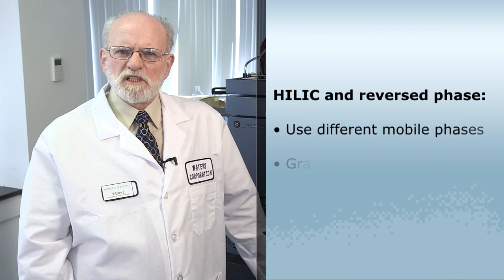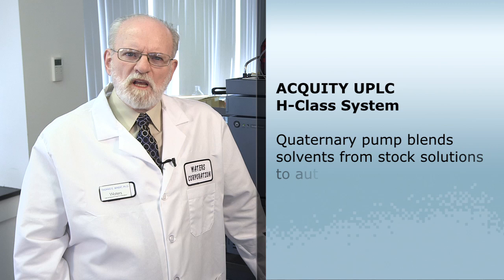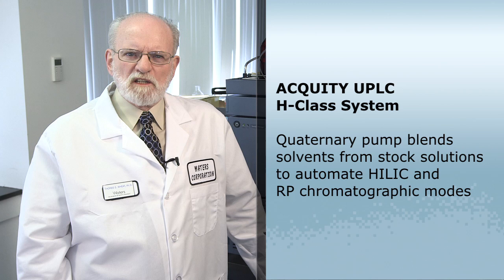HILIC and reverse phase use different mobile phases and the elution gradients are run in opposing directions. To efficiently execute the different methods we choose to use a quaternary blending system, the Acquity UPLC H-class. The pump blends the solvents from stocks as needed for the chromatographic mode in use.